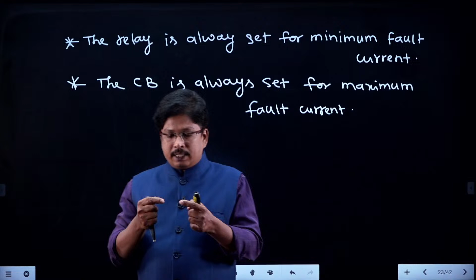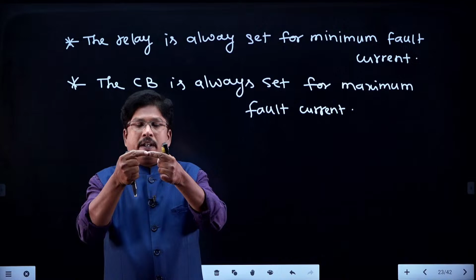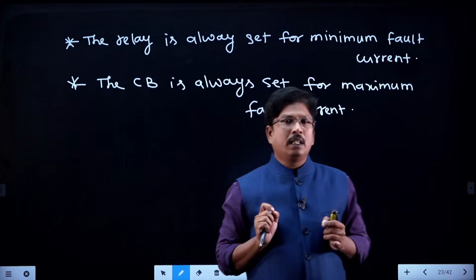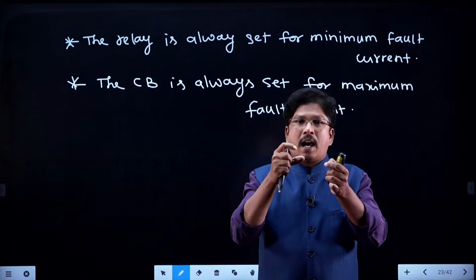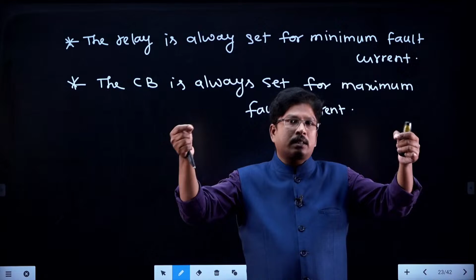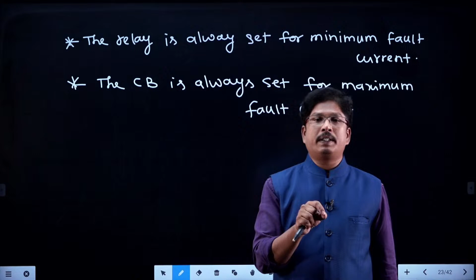The meaning of the setting is, see students, the circuit breaker has to open the contacts. Whenever the contacts open, you are going to experience an arc between the contacts. That arc will damage the circuit breaker contacts. That's why this arc should be minimized, so I need to increase the distance between the circuit breaker contacts. I need to place the largest distance where the circuit breaker will never be damaged. That largest distance will be decided by the largest fault current. That's why the circuit breaker is always set for maximum fault current, and the relay is always set for minimum fault current.